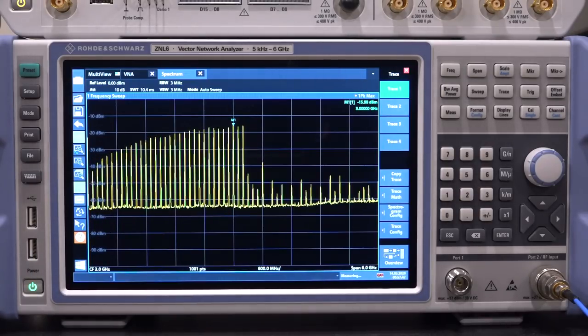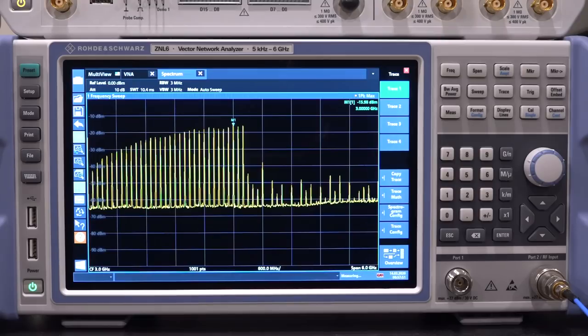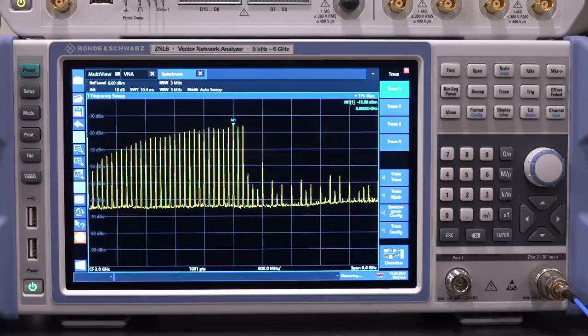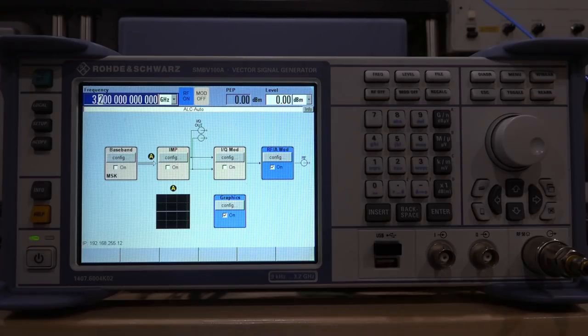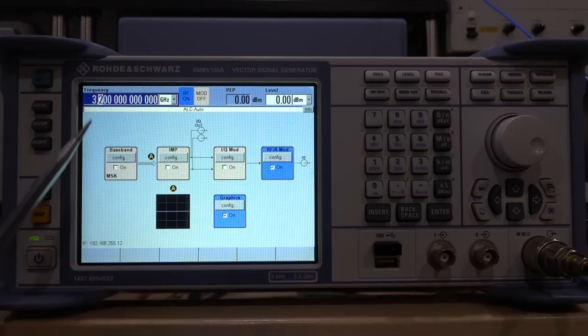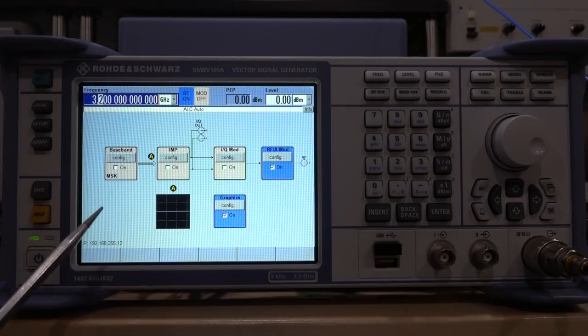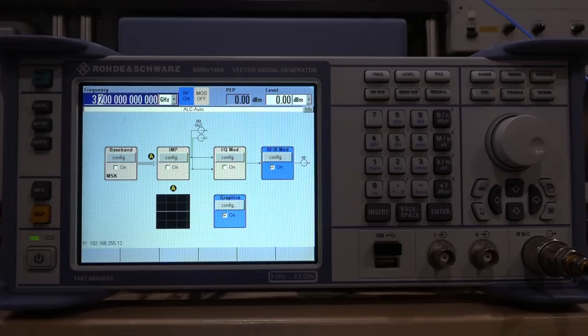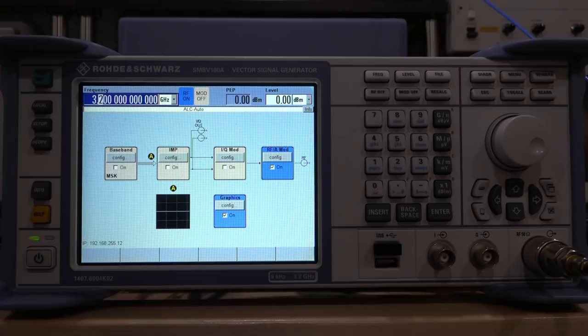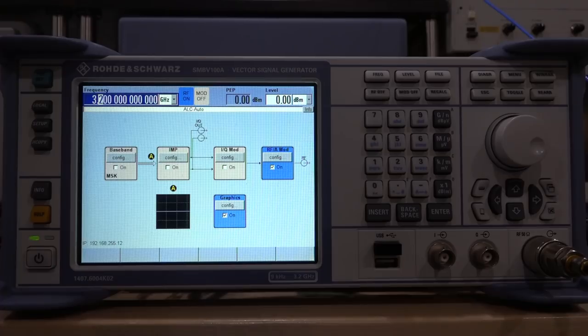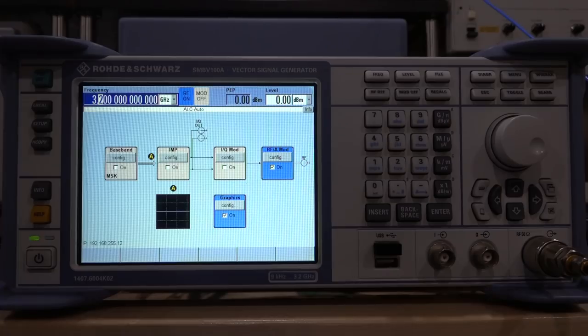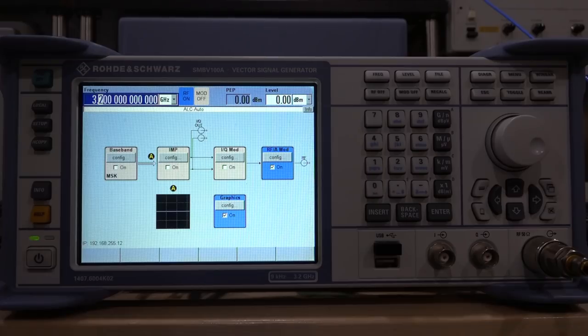So why is that happening? I think in order to understand this, we're going to have to take the unit apart and take a close look at it. But before we do that, let's take a look and see if there's anything in the service manual in terms of block diagram so we can get an understanding of the unit's operation. Now, one thing I forgot to mention, which is quite important, is that the instrument reports absolutely no errors at all. It doesn't say it's unlevel. It doesn't say there's any problem with the RF path. I ran a self-test and everything passed. So the instrument is not even aware that the signal is not present. That actually is a good sign. Believe it or not, that's the best case scenario because it means that the fault is essentially almost at the output of the board because otherwise the instrument would know the ALC loop would be active, the power leveling would be active, which means that it can do all of that and it still doesn't work. So that gives us quite a bit more hint on where to look for the problem.